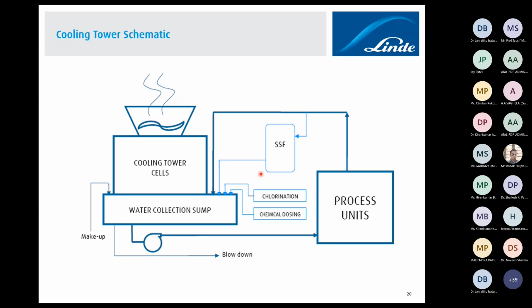So that gives an indication that some biofouling activity is happening, so you need to inject chlorine. It gives an indication of how much, or when, we need to do some shock dosing, and what is the amount of regular chemical dosing we need to maintain everything. I mean, to maintain water TDS well within the limit, chloride level within the limit, and other impurities also within limit. In a subsequent slide, we will see various parameters of the water and how they impact the cooling tower operation.